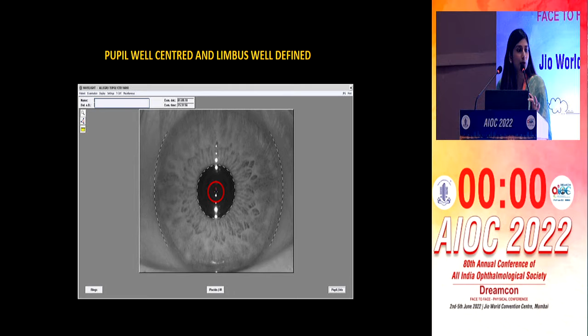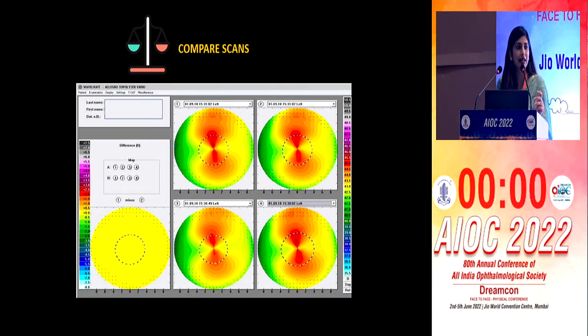After doing all of these, we select 4 different scans of the same eye, like seen here in the image, and then we compare the scans to see for any difference in the K reading. Here, this is an image, so I won't be able to show it to you, but if you put your cursor on any one point here, it will show the K reading difference between the two scans. If this difference is less than 0.75 diopters at a given point, the scans are comparable and can be very well taken for the planning.